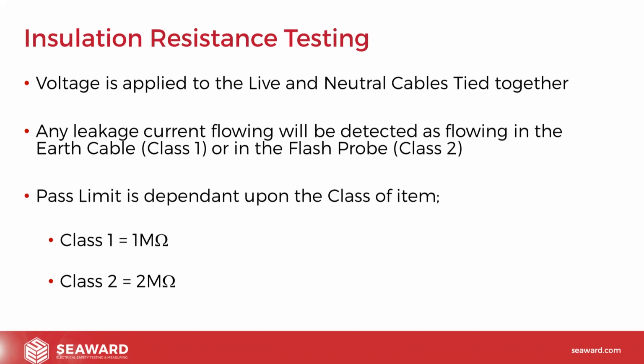So as we discussed, voltage is applied to the live and neutral cables tied together, and then any current flowing back will be detected either within the earth cable itself or within the flash probe. Typically pass limits are set and are quite simple to remember. If we're measuring a class 1 device, our limit will be 1 megohm. If we're measuring a class 2 device, our limit would be 2 meg. So nice and easy to remember.